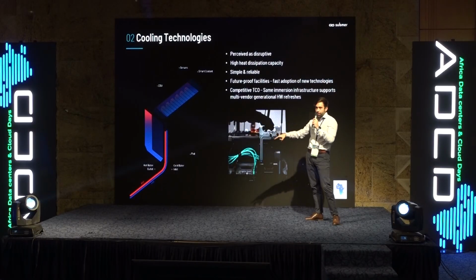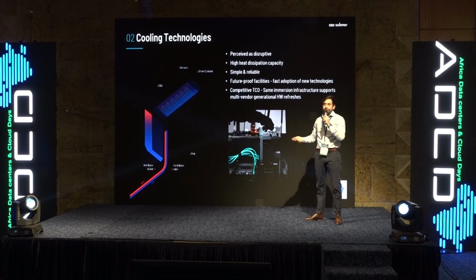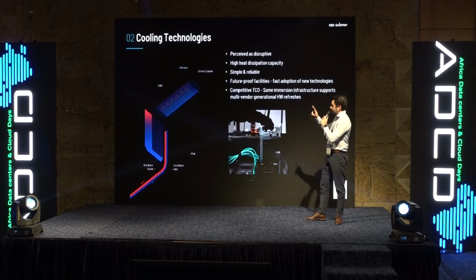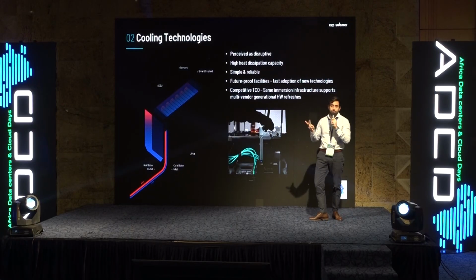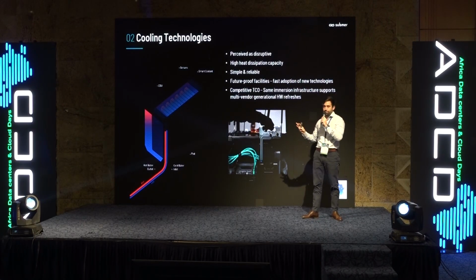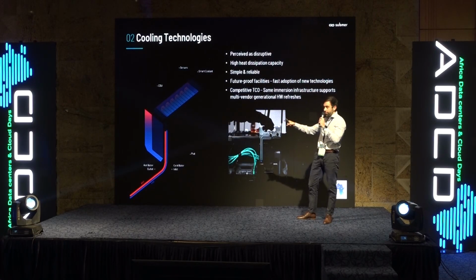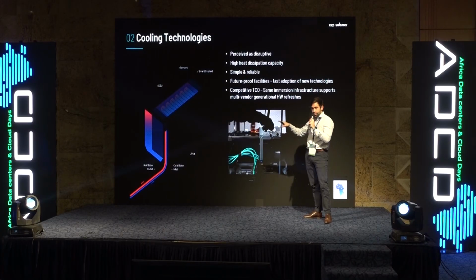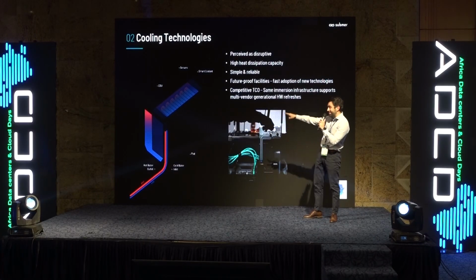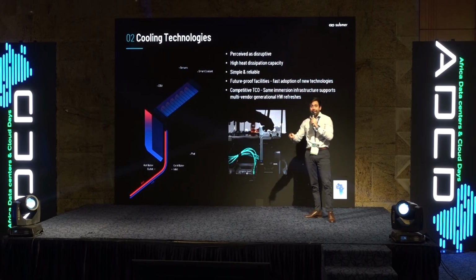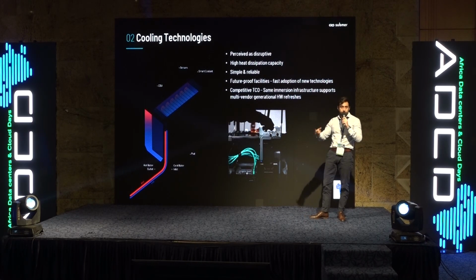And then you have the water loop, similar to the one in an air-cooled data center. In this technology there are three heat transfers: the first from the server to the dielectric fluid, the second in the CDU from the fluid to the water loop, and the last from the water loop to the ambient.